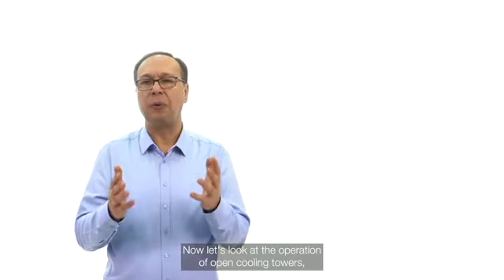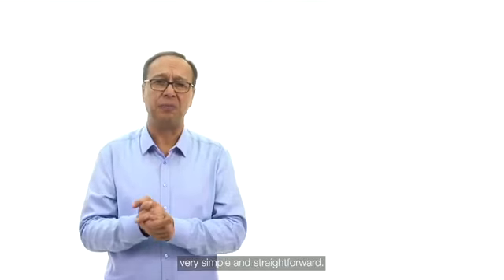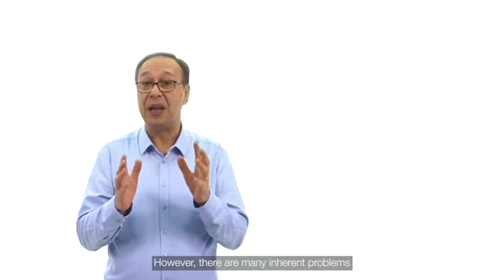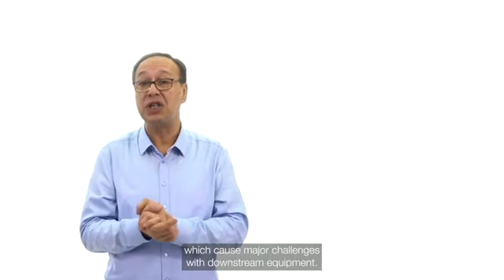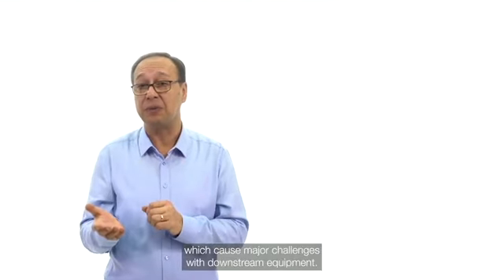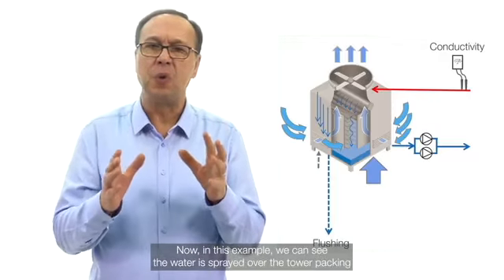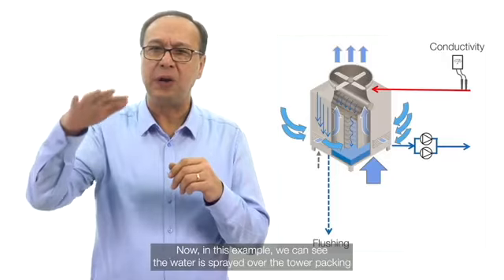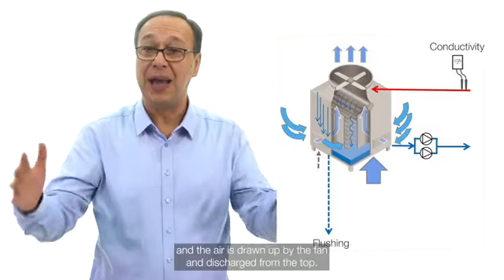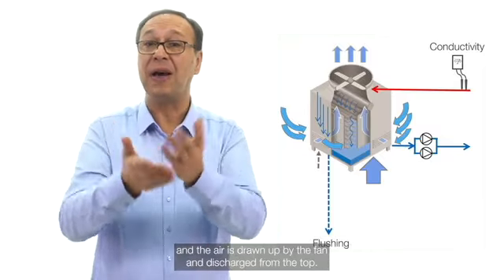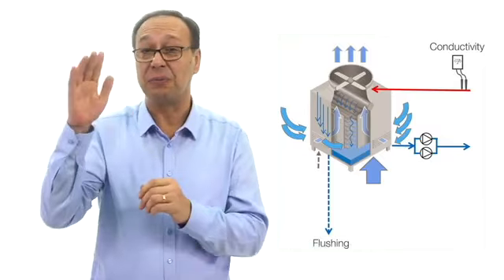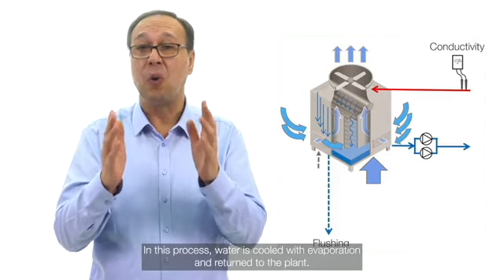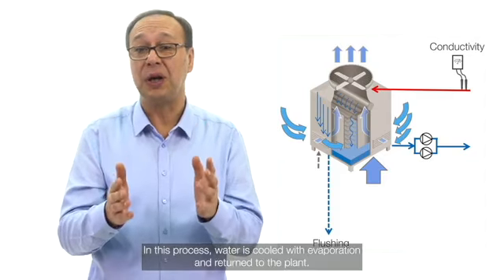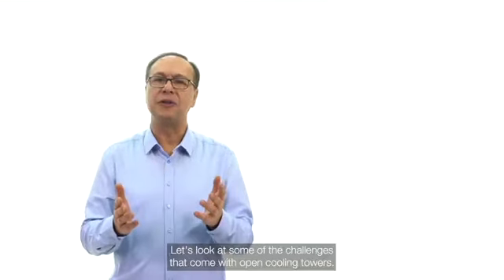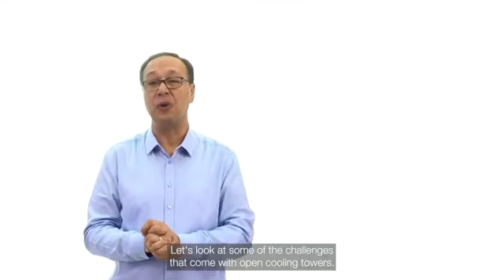Now let's look at the operation of open cooling towers. Very simple and straightforward. However, there are many inherent problems which cause major challenges with downstream equipment. Now in this example, we can see the water is sprayed over the tower packing and the air is drawn up by the fan and discharged from the top. In this process, water is cooled with evaporation and returned to the plant. Let's look at some of the challenges that come with open cooling towers.